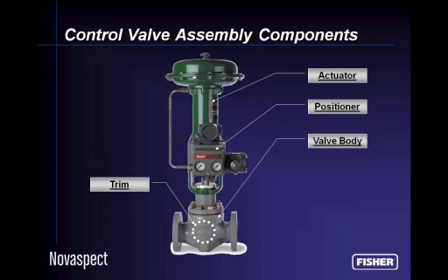A little further deeper into the control valve assembly itself, the actuator is the device that receives a pneumatic signal of varying analog value, typically 3 to 15, 6 to 30 PSIG, 0 to 45 PSIG, whatever we've engineered the actuator to do. And the sole purpose of the actuator is to move the plug in the control valve up and down relative to a seat ring in order to allow a particular flow through the valve. The actuator usually has a fail mechanism, fail open or close, but it does not always have to have that.